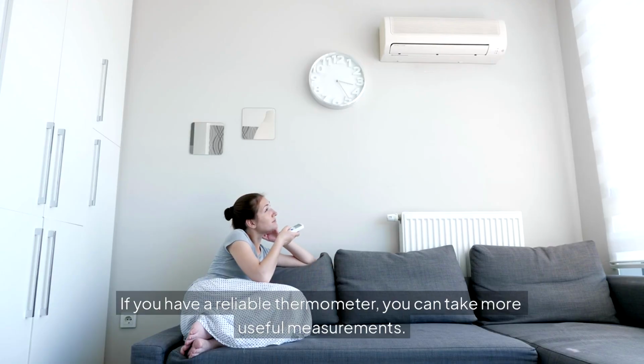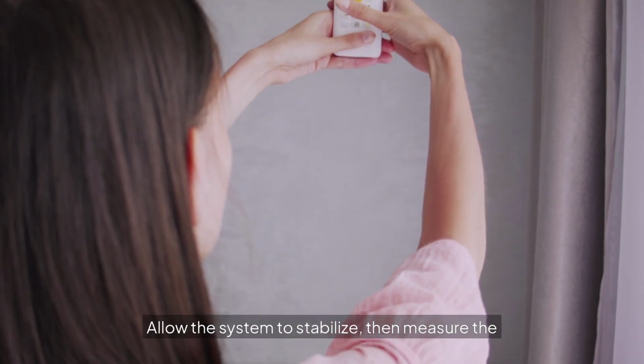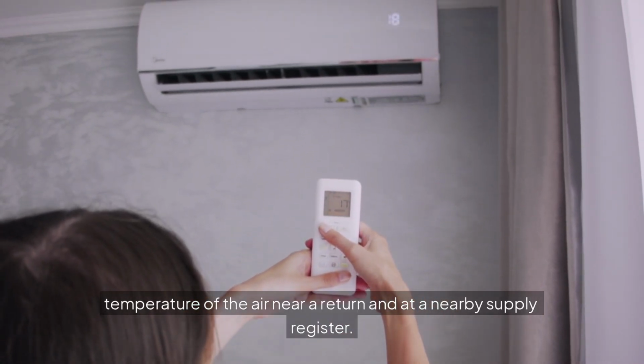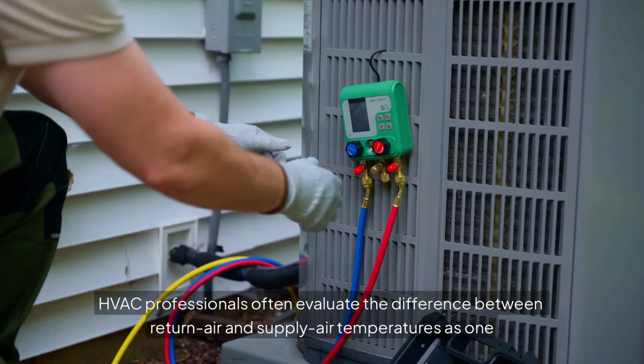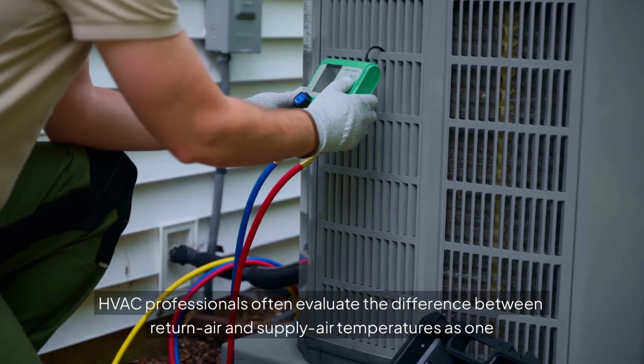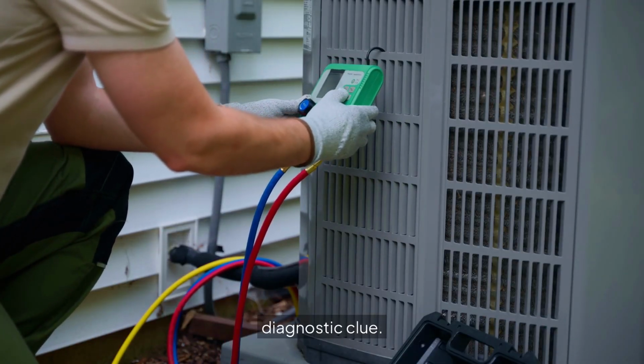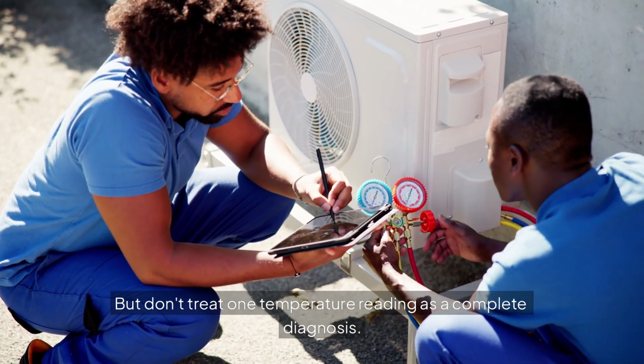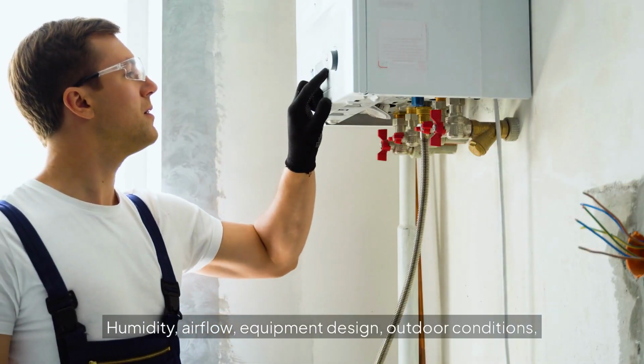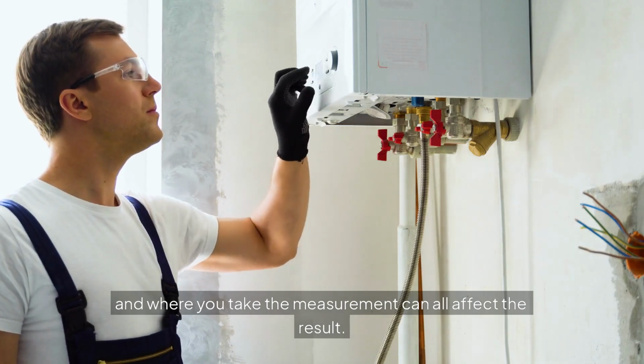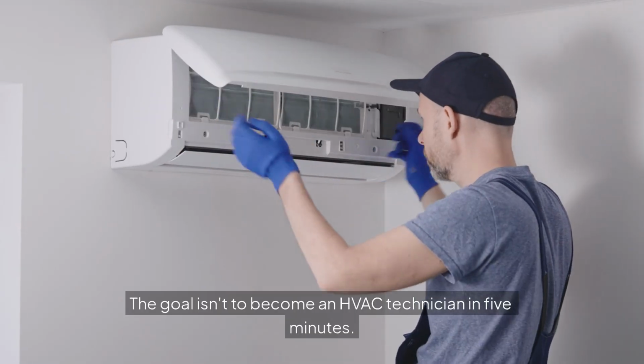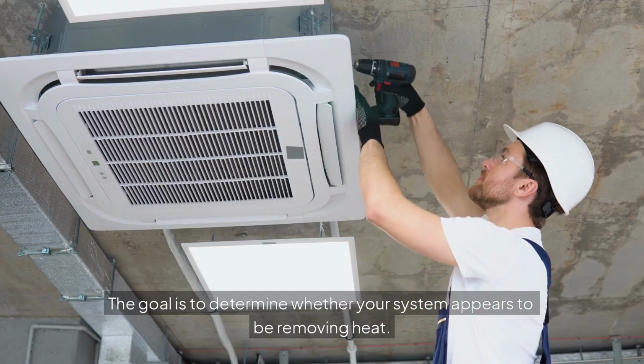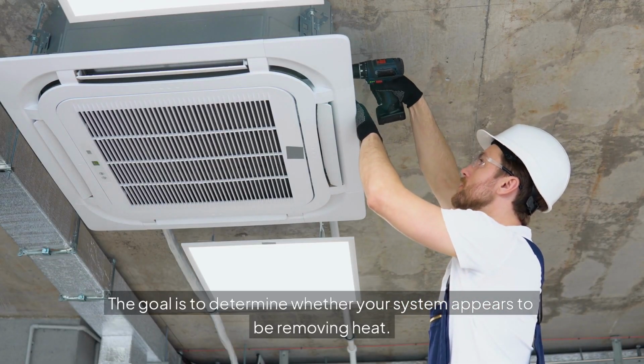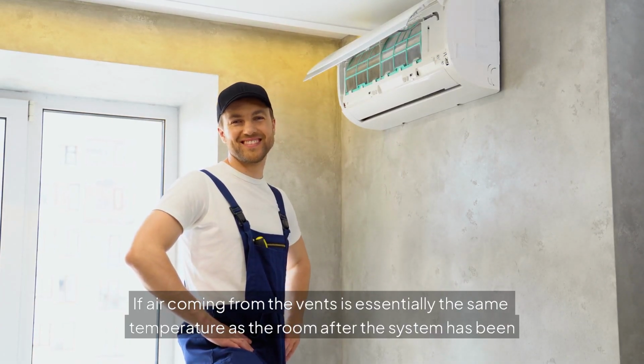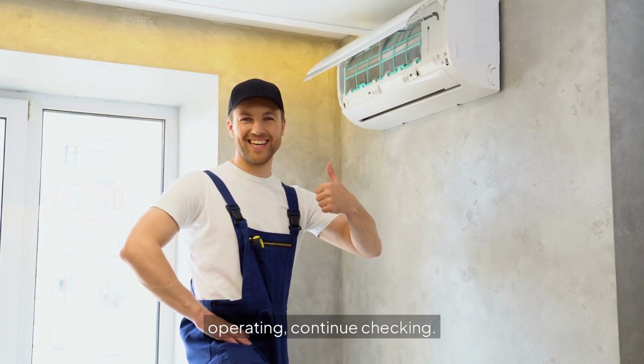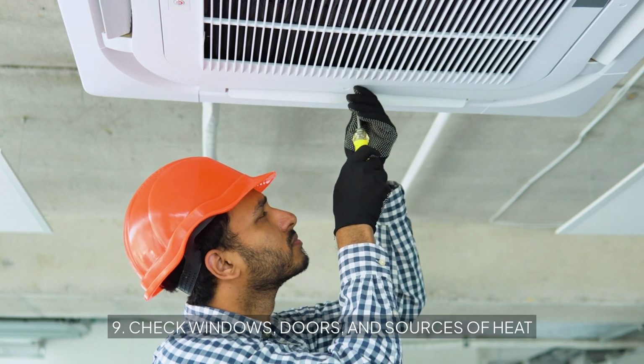If you have a reliable thermometer, you can take more useful measurements. Allow the system to stabilize, then measure the temperature of the air near a return and at a nearby supply register. HVAC professionals often evaluate the difference between return air and supply air temperatures as one diagnostic clue. But don't treat one temperature reading as a complete diagnosis. Humidity, airflow, equipment design, outdoor conditions, and where you take the measurement can all affect the result. The goal isn't to become an HVAC technician in 5 minutes. The goal is to determine whether your system appears to be removing heat. If air coming from the vents is essentially the same temperature as the room after the system has been operating, continue checking.